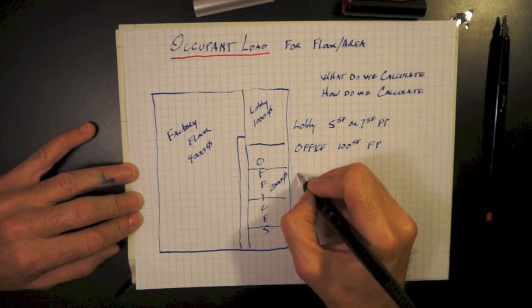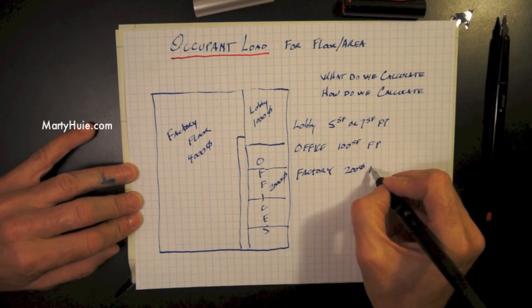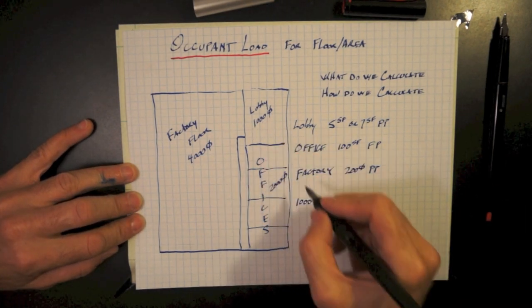Office space falls under business, and that's 100 square feet per person. And the factory floor falls under manufacturing or assembly, and that's 200 square feet per person.